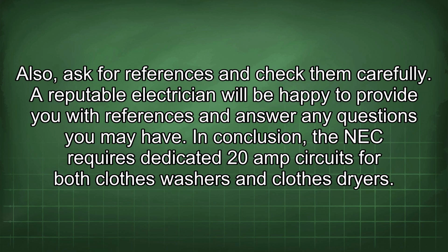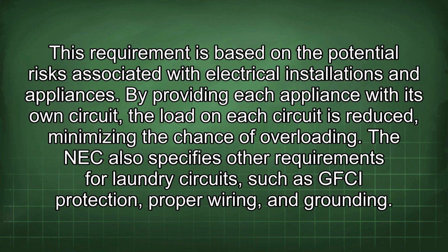In conclusion, the NEC requires dedicated 20-amp circuits for both clothes washers and clothes dryers. This requirement is based on the potential risks associated with electrical installations and appliances. By providing each appliance with its own circuit, the load on each circuit is reduced, minimizing the chance of overloading. The NEC also specifies other requirements for laundry circuits, such as GFCI protection, proper wiring, and grounding.